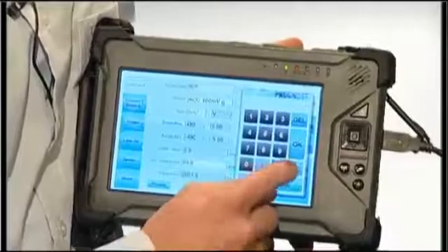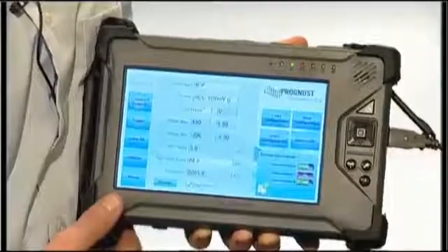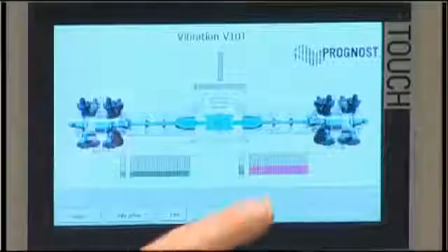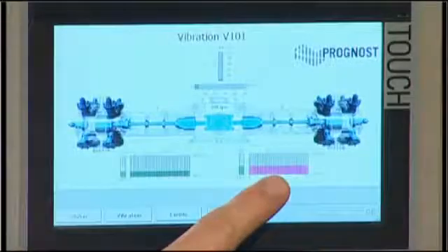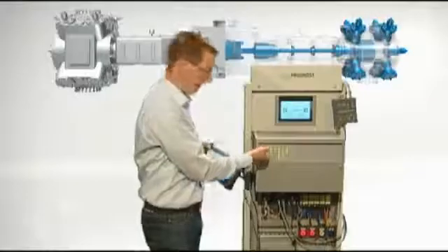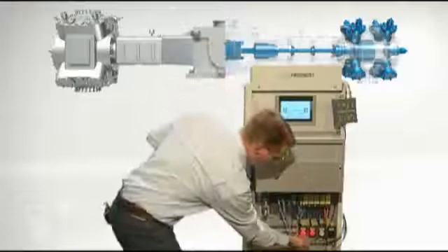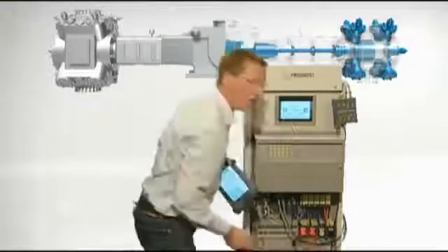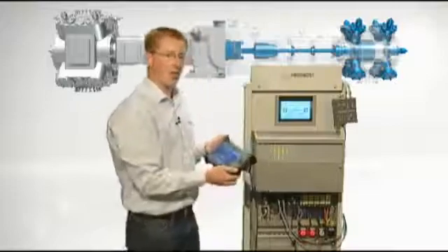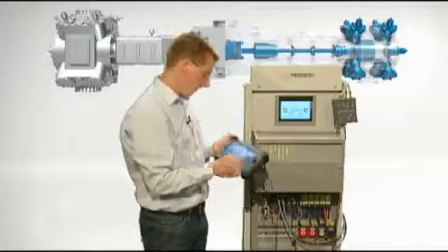We will apply directly an 80 meter per square second value, which in this case does violate the safety limits, visible on screen in a machinery 1 safety limit violation, as well as on the relay output, where we see alert and shutdown are in violation. Okay, we've now found out this safety loop works effectively.